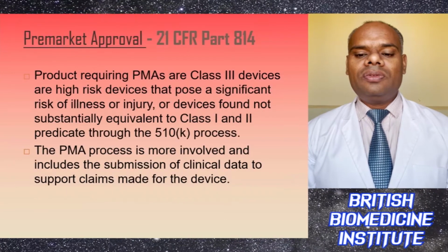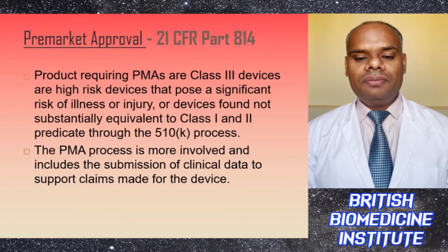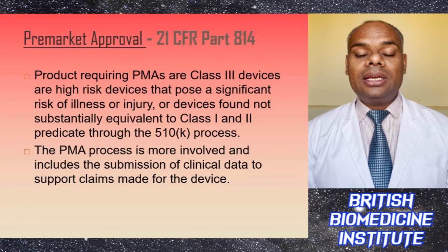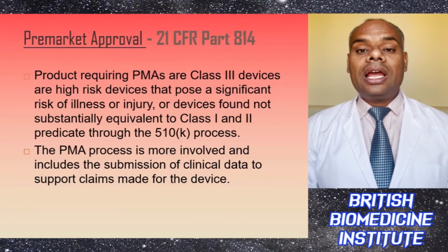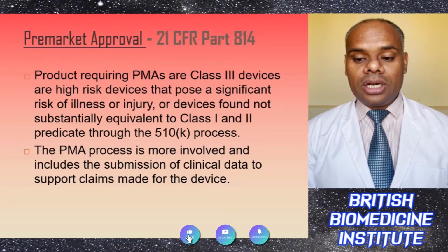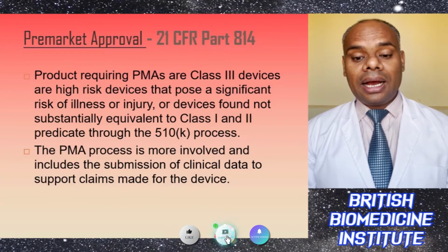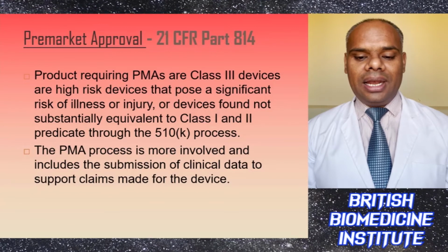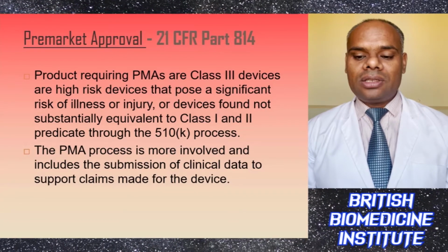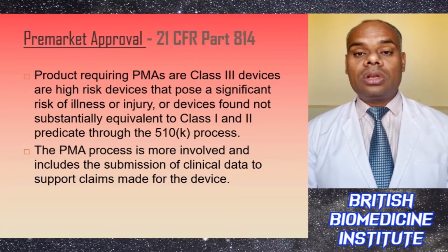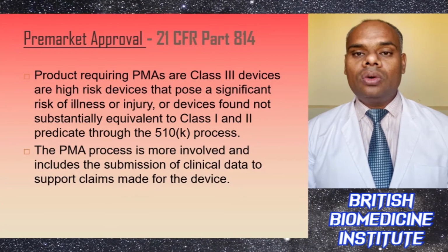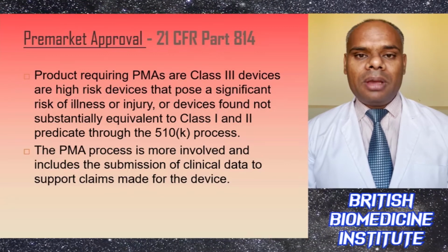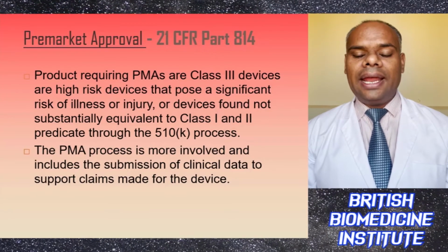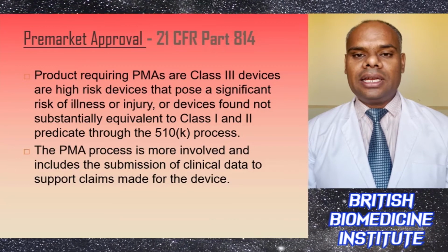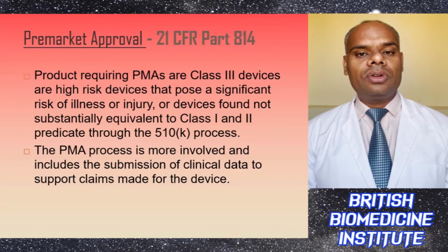So in accordance with 21 CFR Part 814, this is basically pre-market approval. Products which require pre-market approval are class 3 devices, because they are high-risk devices which pose a significant risk of illness or injury, and devices found not substantially equivalent to a class 1 or 2 predicate through the 510K process. The PMA process is more involved and includes the submission of clinical data to support claims made for the devices.